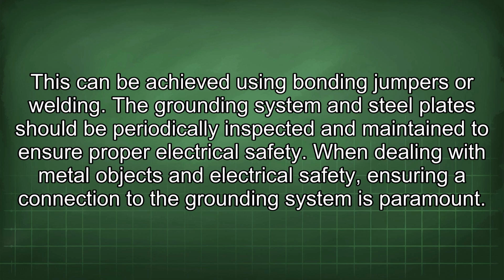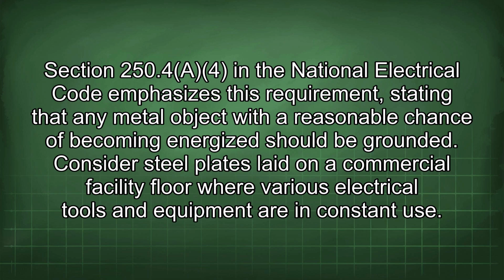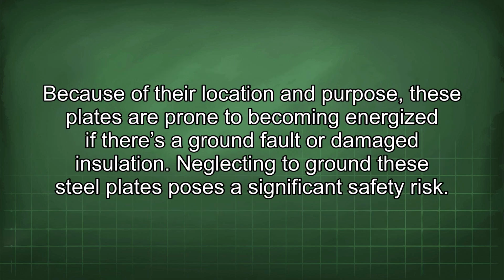When dealing with metal objects and electrical safety, ensuring a connection to the grounding system is paramount. Section 250.4(A)(4) in the National Electrical Code emphasizes this requirement, stating that any metal object with a reasonable chance of becoming energized should be grounded. Consider steel plates laid on a commercial facility floor where various electrical tools and equipment are in constant use. Because of their location and purpose, these plates are prone to becoming energized if there's a ground fault or damaged insulation. Neglecting to ground these steel plates poses a significant safety risk.